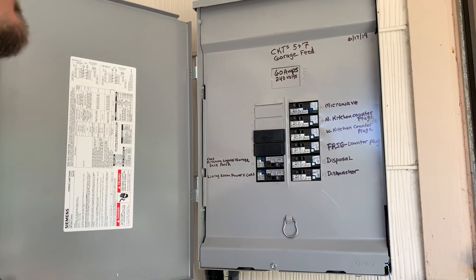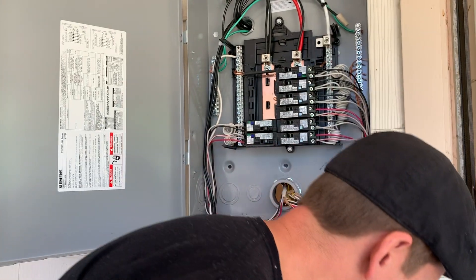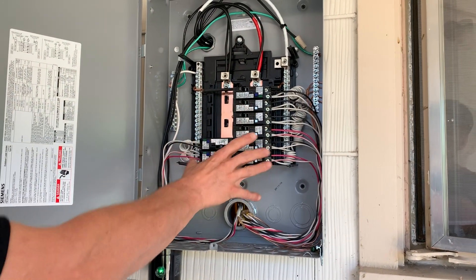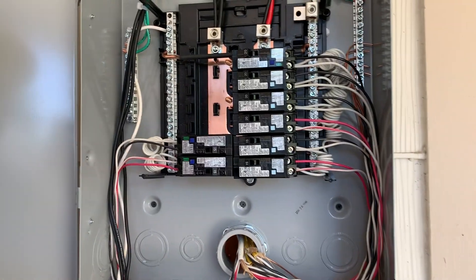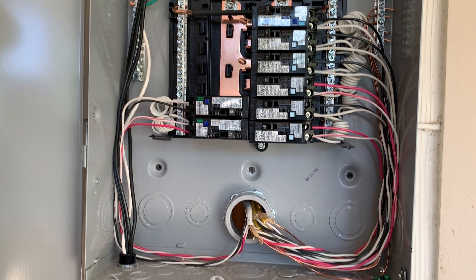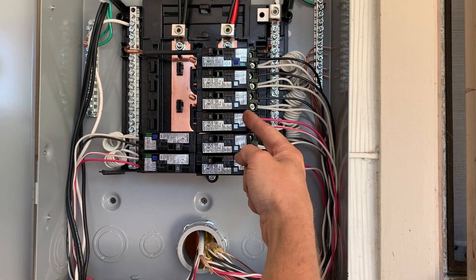Think of it like not having enough trunk space in your car. Per Article 230.79, it's adequate to have 100 amps to the home — it's just that you can tap a sub-panel. You can tap and step down to 60 amps. In this job, all these arc faults had to be added for just this kitchen because they were tripping from an overload, dead shorts, or ground faulting — due to wires melting in the boxes.